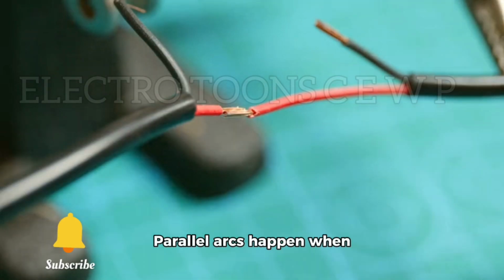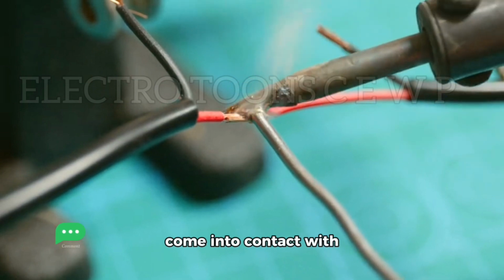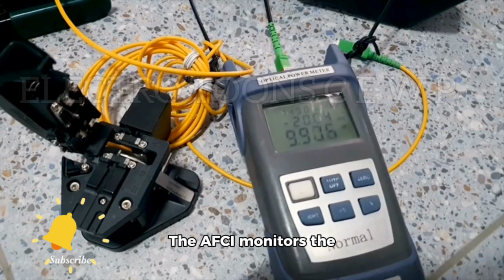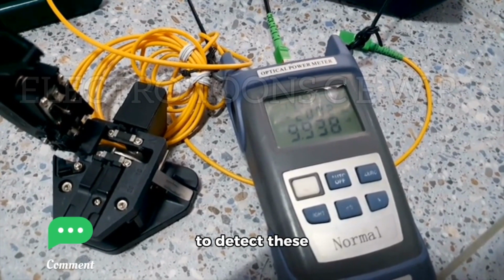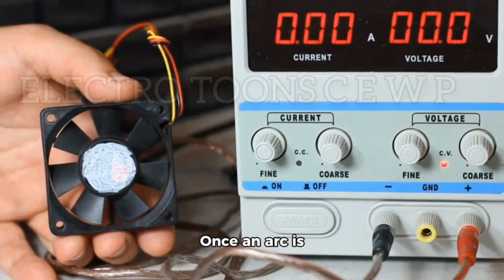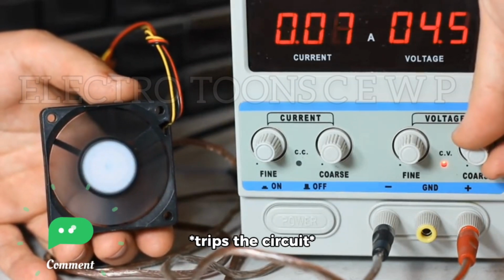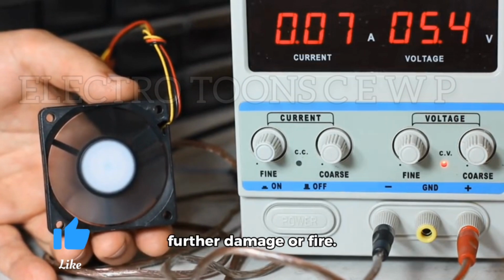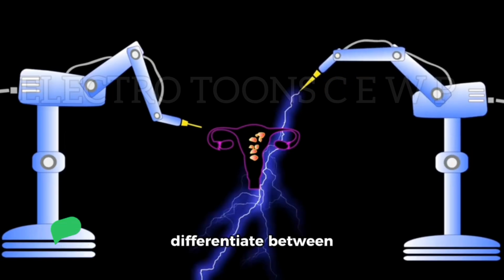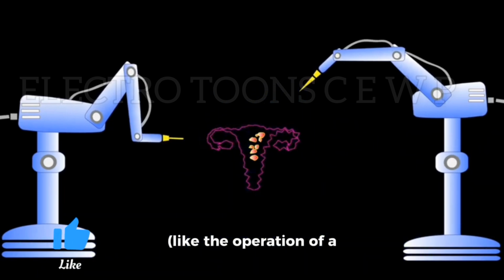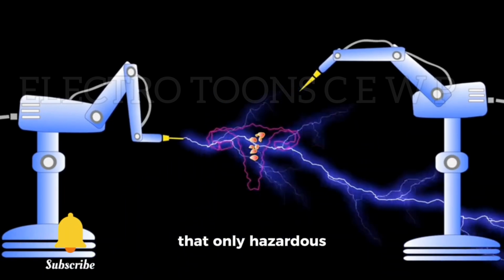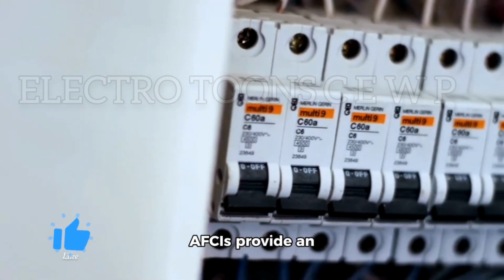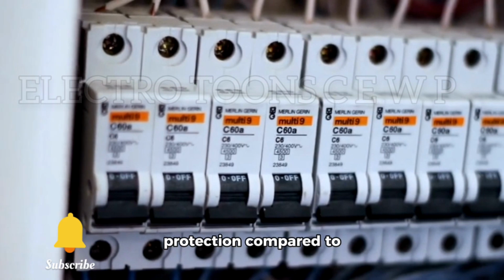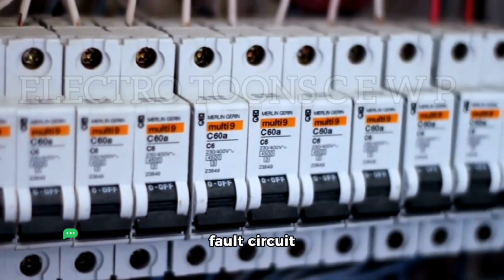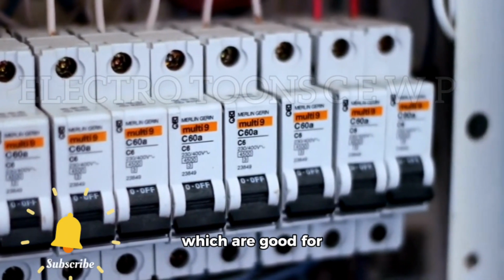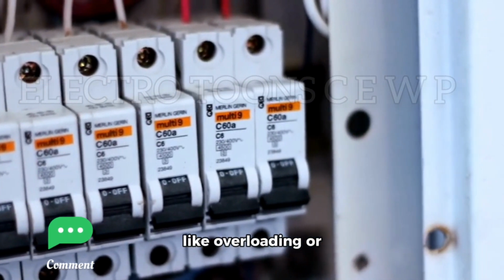Parallel arcs happen when the hot and neutral wires come into contact with each other or another conductive material. The AFCI monitors the voltage and current flow to detect these potentially dangerous conditions. Once an arc is detected, the AFCI trips the circuit and cuts off the power, preventing further damage or fire. The AFCI can differentiate between normal electrical events like the operation of a motor or a switch and dangerous arcs, ensuring that only hazardous situations result in a trip. AFCIs provide an additional layer of protection compared to standard circuit breakers and ground fault circuit interrupters (GFCIs), which are good for detecting other hazards like overloading or ground faults but do not address arc faults.